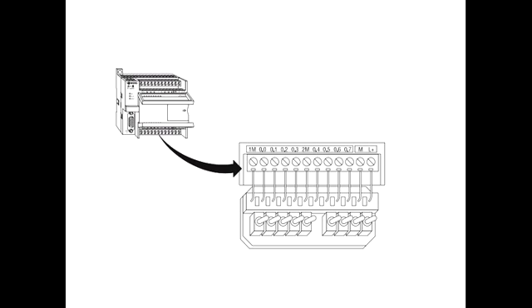Switches are wired between the 24VDC power supply, L+, and the inputs. For example, the switch on the far left is wired between the first input, I0.0, and L+.